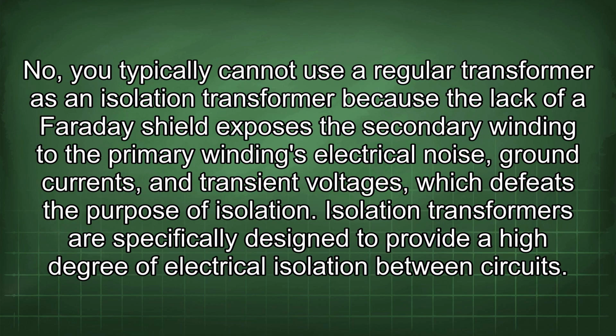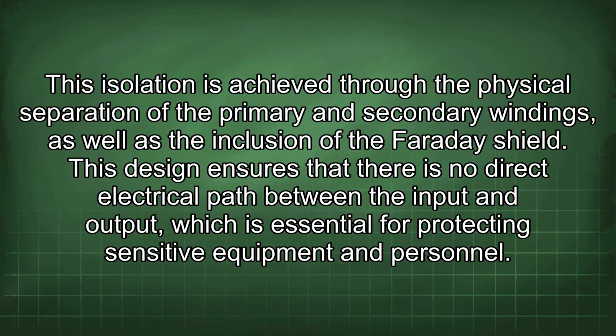No, you typically cannot use a regular transformer as an isolation transformer because the lack of a Faraday shield exposes the secondary winding to the primary winding's electrical noise, ground currents, and transient voltages, which defeats the purpose of isolation. Isolation transformers are specifically designed to provide a high degree of electrical isolation between circuits. This isolation is achieved through the physical separation of the primary and secondary windings, as well as the inclusion of the Faraday shield. This design ensures that there is no direct electrical path between the input and output, which is essential for protecting sensitive equipment and personnel.